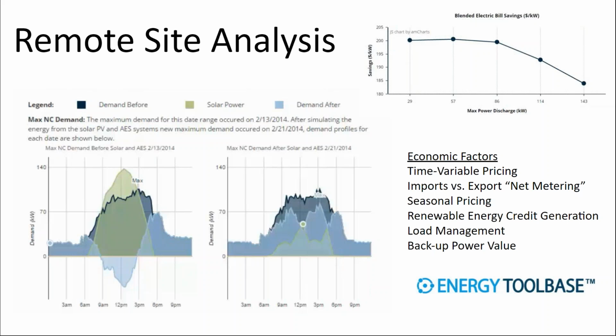So if you had a target of 50 kilowatts, but your battery was too small and it ran up to 80 kilowatts, it'll look ahead for the rest of the month by readjusting that new target. So it has a little bit more intelligent modeling than what you can do on your own. That said, that's why we spent so much time yesterday testing out different extrema, because that's really all they're doing, the same thing, but with equations rather than brute force.